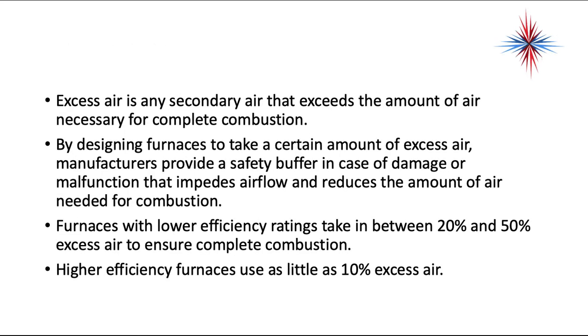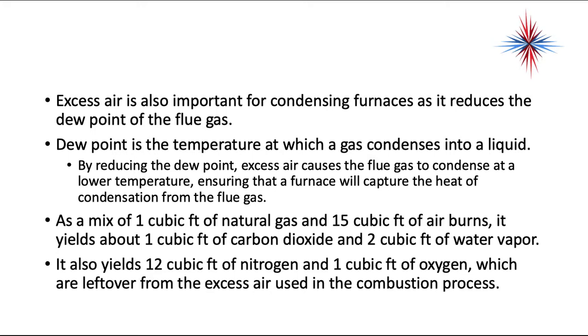Excess air is any secondary air that exceeds the amount needed for complete combustion. By designing furnaces to take a certain amount of excess air, manufacturers provide a safety buffer in case of damage or malfunction that reduces airflow. Furnaces with lower efficiency ratings take between 20 and 50% excess air to ensure complete combustion. Higher efficiency furnaces use as little as 10% excess air. Excess air is also important for condensing furnaces as it reduces the dew point of the flue gas — the temperature at which gas condenses to a liquid.